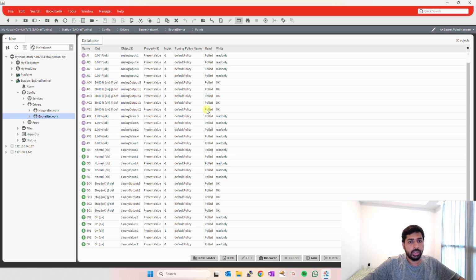Now consider this just being 30. Now consider you have a facility with 10,000 points. Every 10 seconds you're sending out 10,000 packets to and from your supervisor to your controllers, where there is a tree architecture, with all the controllers going to one network switch, that network switch going to another network switch, and that network switch coming back to your supervisor. You see where there would be a choke in this architecture, where you're sending 10,000 packets every 10 seconds.